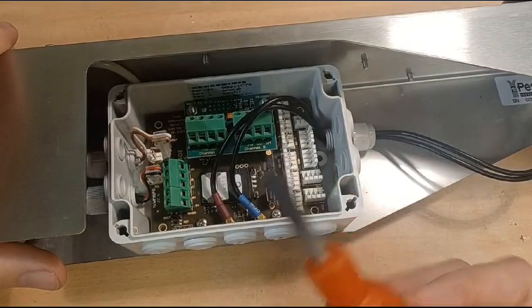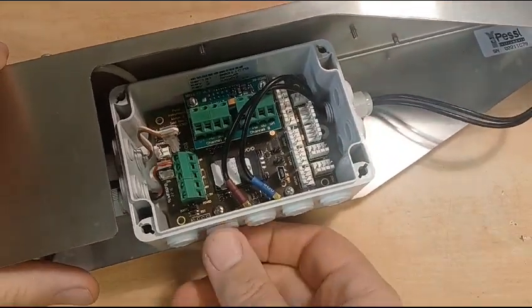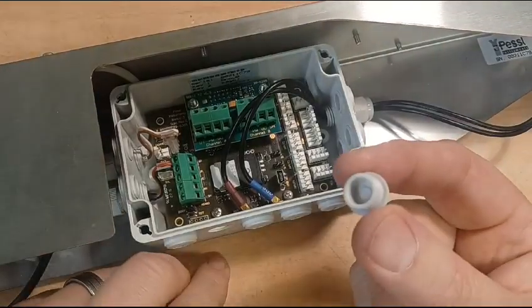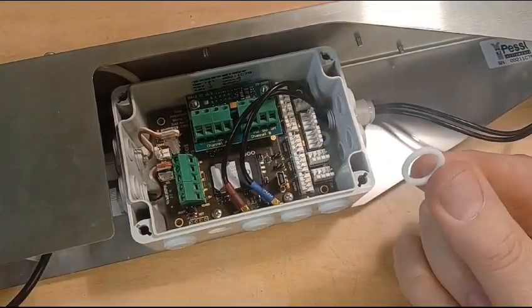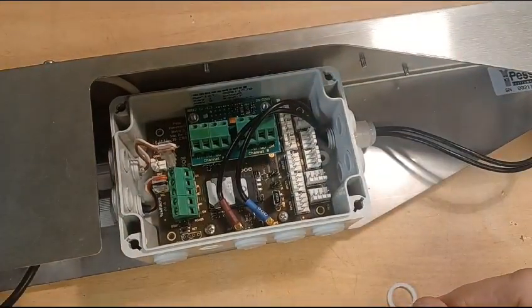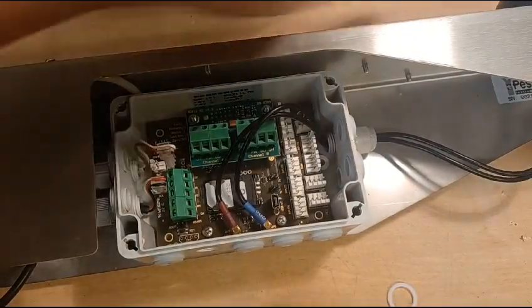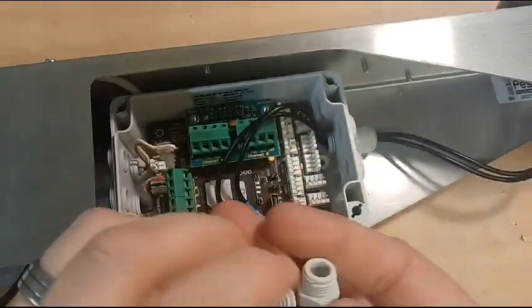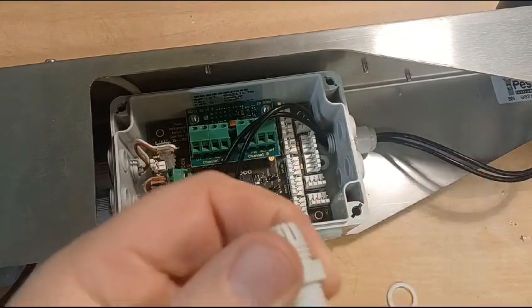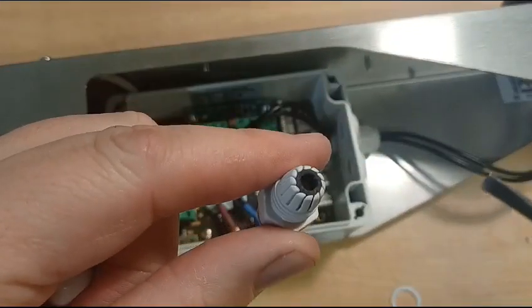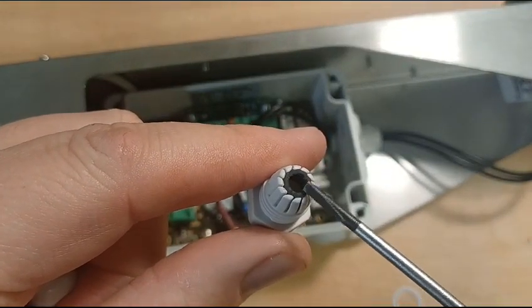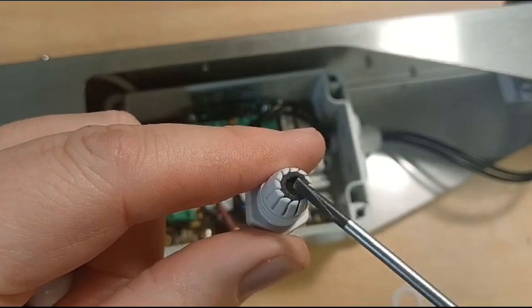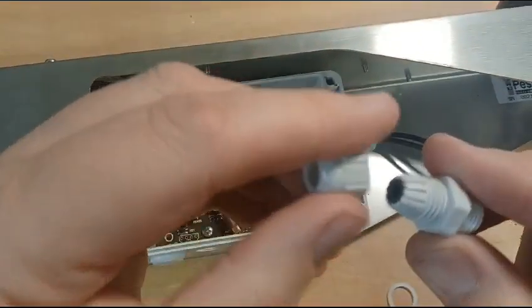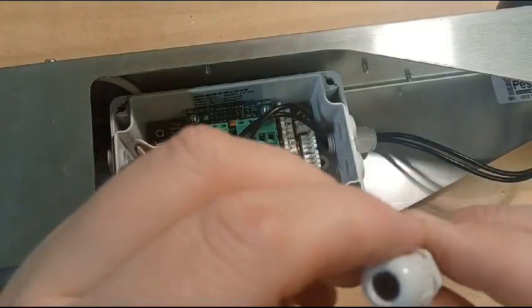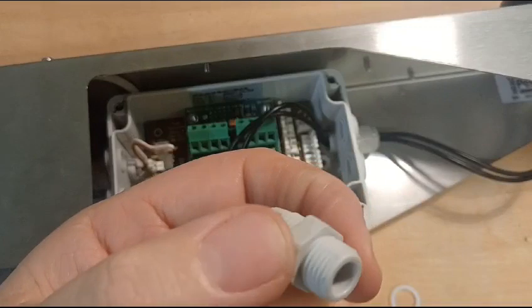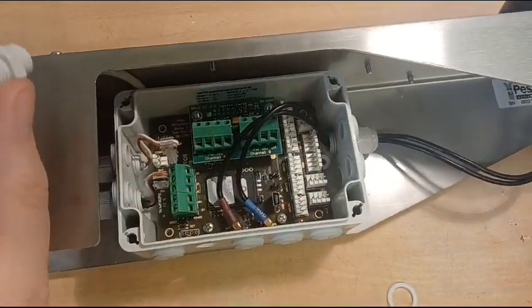So again, flat bladed screwdriver, take the plug out, keep the cap as a spare. We'll use this one because there is no gland on this cable, which you often find, so always make sure you have plenty of these. Also make sure, very important, that the rubber collar is inside this slotted opening, because when you tighten the cap to hold the cable, it pinches the rubber, which obviously seals it from moisture and bugs and stuff like that, which do cause issues.